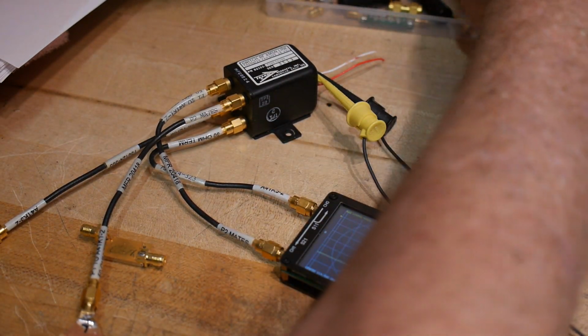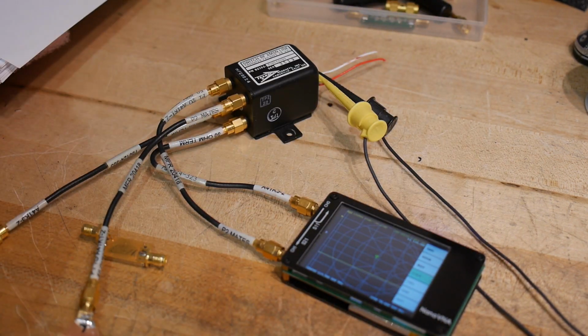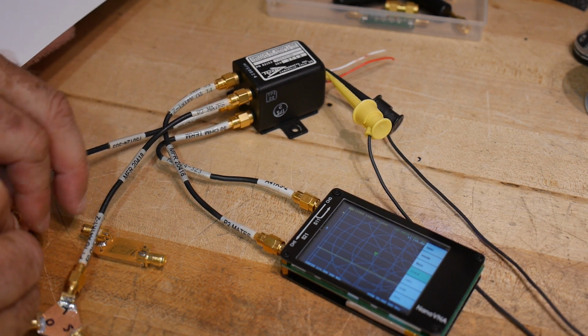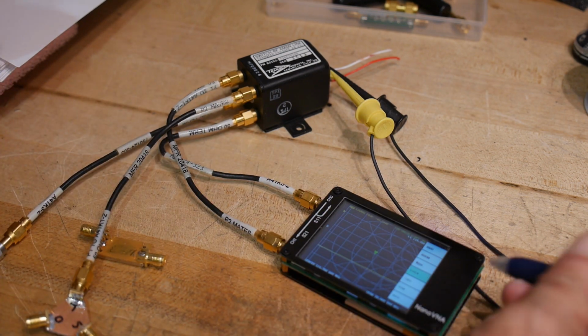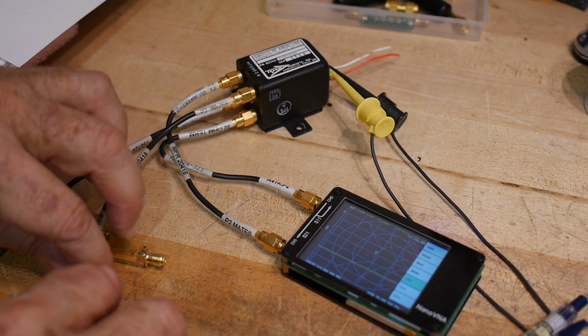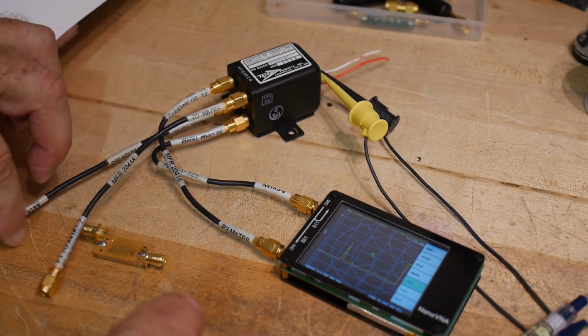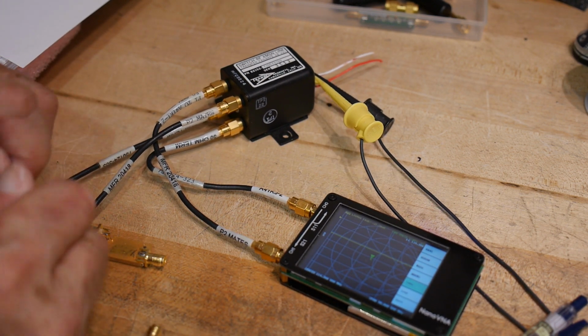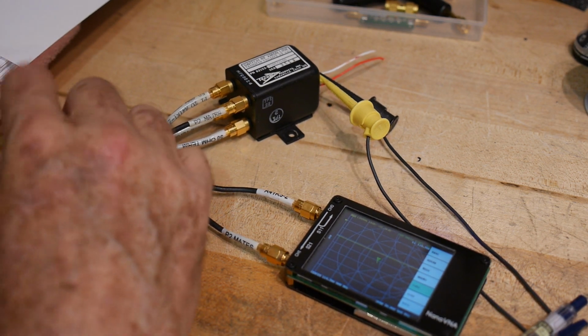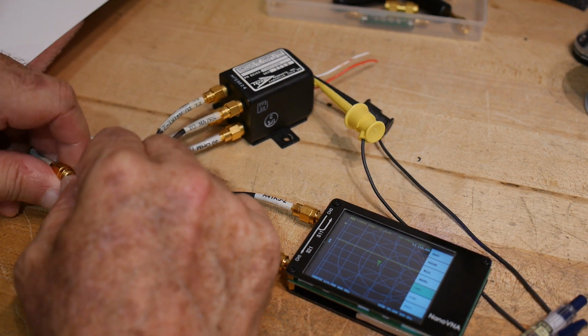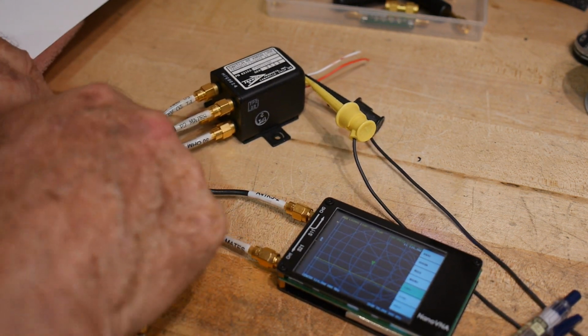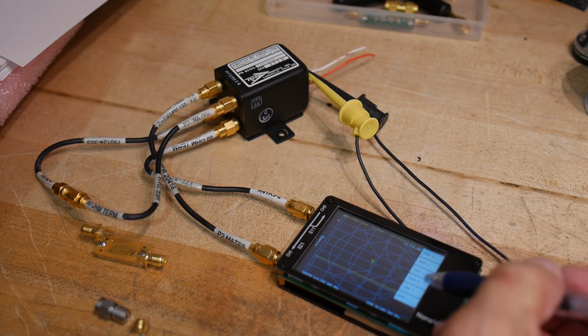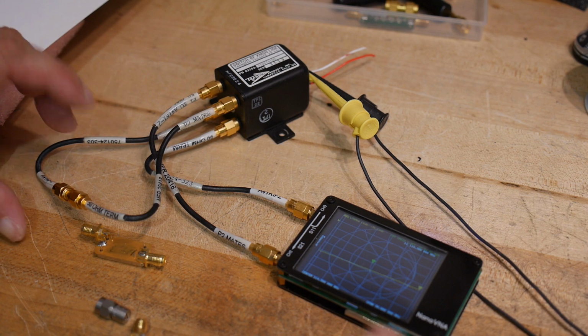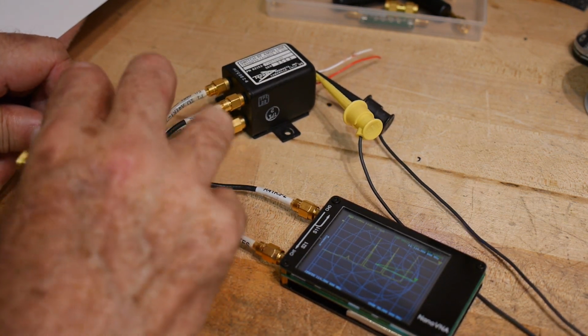Load. We need to do an isolation, so I need another load. I need to make another female load. I just have to use a little adapter here. Shouldn't affect this measurement very much. Okay, so we'll do an isolation. Now we need to do a through. Through and done. And we're going to save this in number 4. And let's get this out of the way.